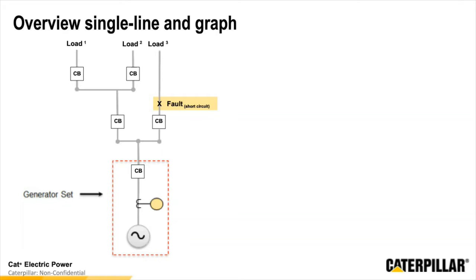Inside the red bounding box is what we would consider on package within the generator. The circle at the bottom represents our generator set itself. And then up from that is a protective relay that we'll discuss here in just a couple more slides. As we move further up, we have the circuit breaker inside the square, which is our on-package circuit breaker. So this is our overall and generator set together. As we move up the drawing, we see that there are 3 different loads. Each has multiple different circuit breakers protecting those different paths of power. And each of those different zones in between the circuit breakers is what we're going to consider as our protection zones. So we're going to be talking about how we manage those protective zones and making sure that we're managing the overall system.